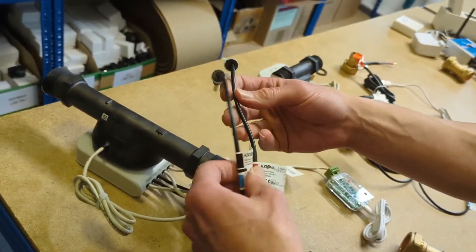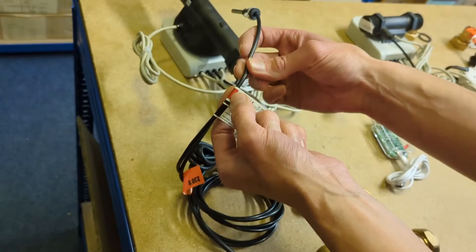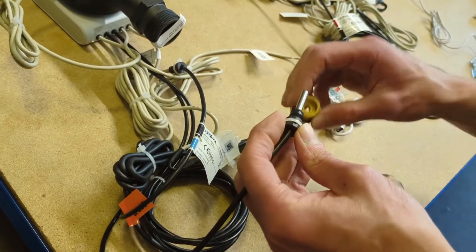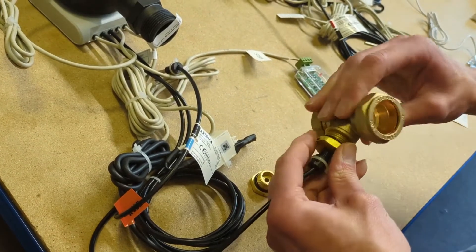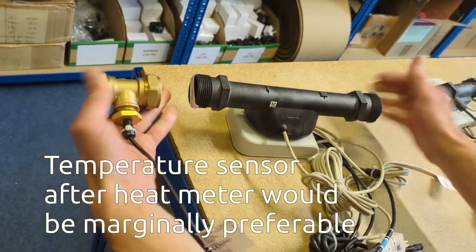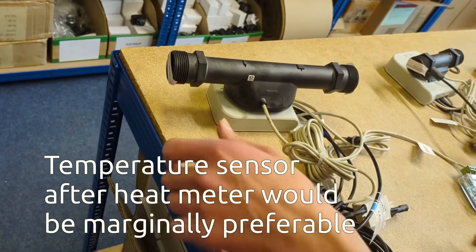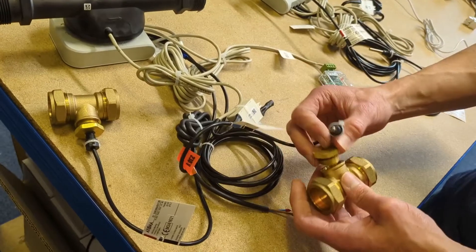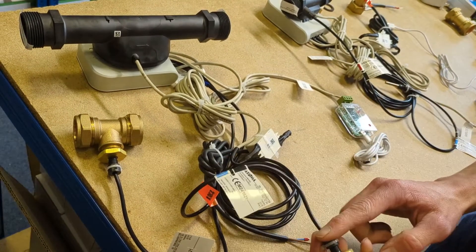That just means we're going to have to install two temperature sensors. The one marked with a red tag needs to go on the flow, and as the sticker says, the heat meter body also needs to go on the flow. When you're installing this, screw the M10 thread into the one inch T and put this in line with the heat meter, either before or after. It doesn't matter. And then the return temperature sensor would go on the primary return, just install a second T.